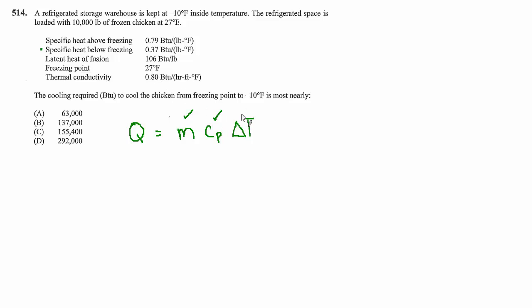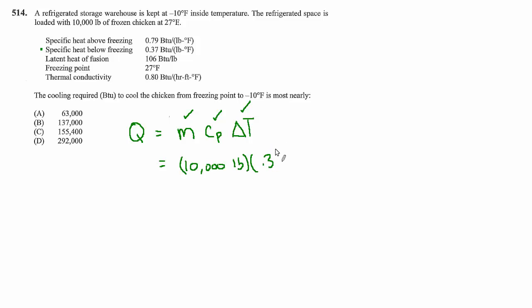And I'll keep the units 10,000 pounds, 0.37 BTU per pound degree Fahrenheit and a delta T of 27 degrees Fahrenheit minus negative 10 degrees Fahrenheit.